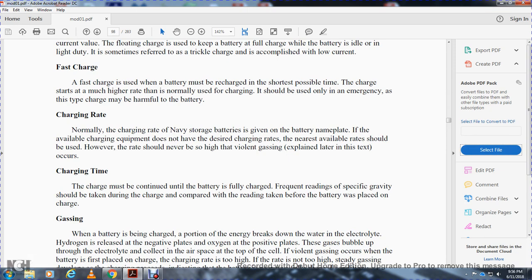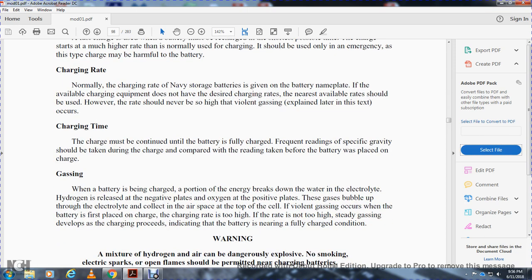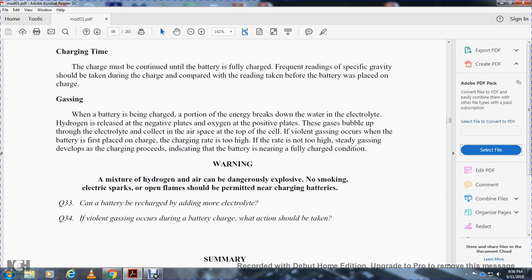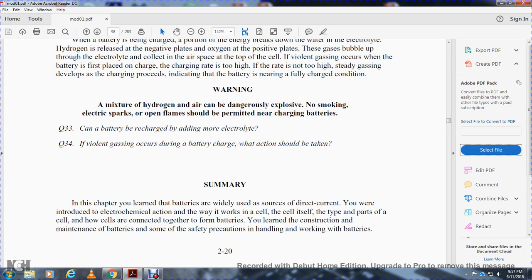The charging rate should never be so high that violent gassing occurs. Charging must be continued until the battery is fully charged; frequent readings of specific gravity should be taken. Gassing: when a battery is being charged, some energy breaks down the water in the electrolyte — hydrogen is released at the negative plate and oxygen at the positive plate; gas bubbles up through the electrolyte and collects in the airspace at the top of the cell. If the charging rate is too high, violent gassing occurs immediately. Warning: a mixture of hydrogen and air can be dangerously explosive; no smoking, electrical sparks, or open flames should be permitted near charging batteries.